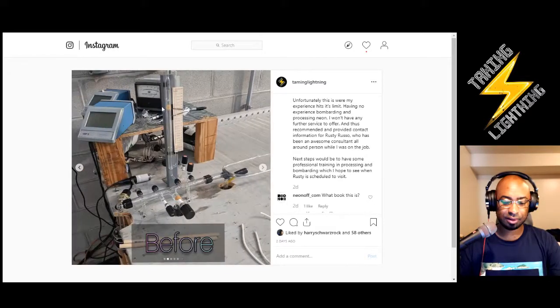So the first thing you remove is we took away this little shelf that wasn't needed to be there, and we didn't need this oil gauge because we already had a gauge that can read to the torr and read microns. So we only needed these two devices over here, and it just kept everything easier.